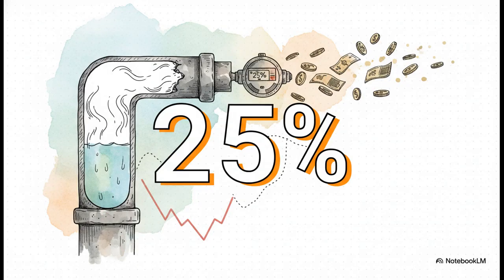And the financial damage? Whoa, it is staggering. Technical studies have confirmed that if a pipe is just 1/4 full of air, your meter can over-register your usage by 25%, or even more. Think about that. That's a massive overcharge for something you never, ever received.